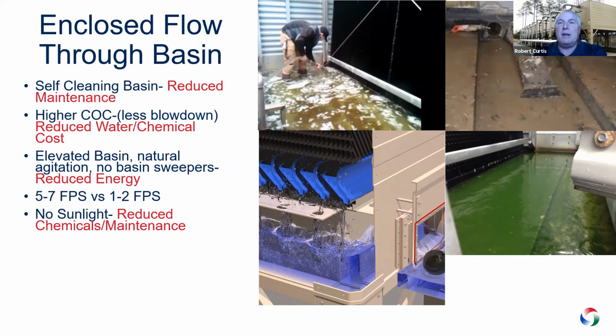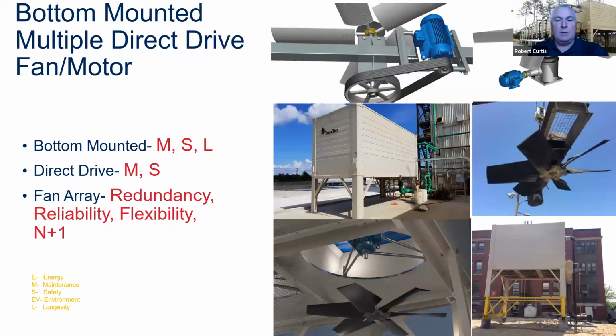And then because the basin's elevated and we're moving that water so fast, you do not need basin sweeping systems. So you don't have to have the cost of operation year round of a basin sweeping system. And then that reduced light, eliminating the sunlight, out of the tower now reduces the biocide demand. So you have less chemicals required in that. So that enclosed flow-through basin design really is a true shift in the way that things had been done and solved a lot of problems, or challenges we were given to solve some issues.